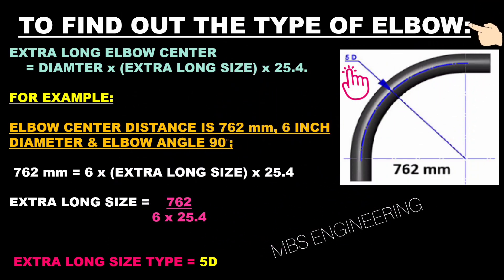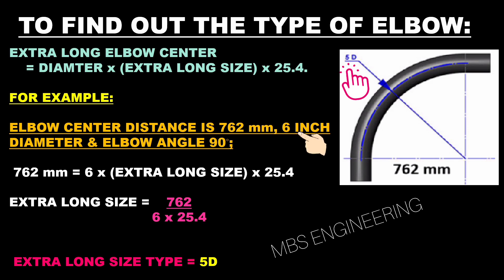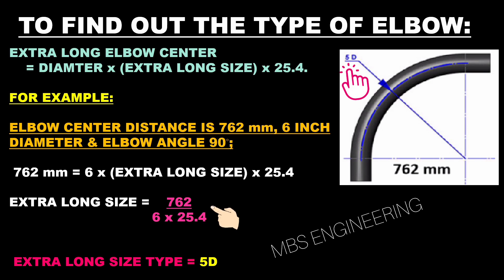Next, we learn how to find the type of elbow given a known center distance. The formula is: Extra Long Elbow Center = D × Extra Long Size × 25.4. Given: elbow center distance = 762 mm, diameter = 6 inches, elbow angle = 90 degrees. Applying the data: 762 = 6 × Extra Long Size × 25.4. Therefore, Extra Long Size = 762 ÷ (6 × 25.4) = 5D.